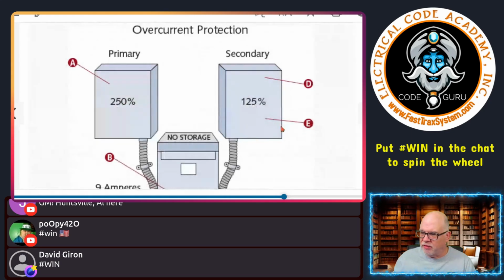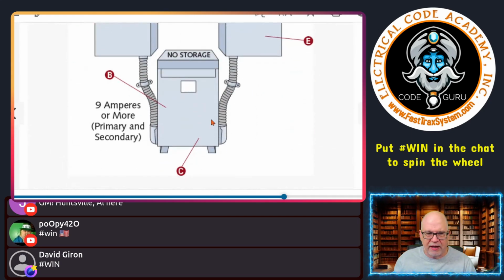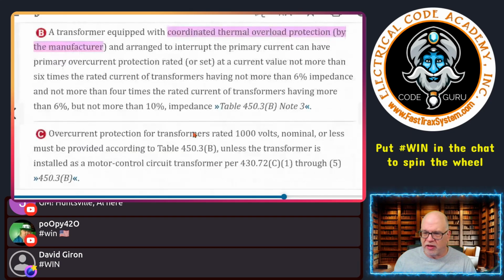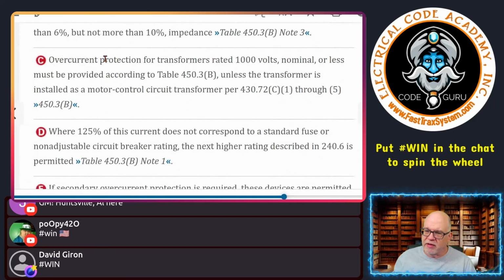C is pointing out, let's see, where's C at here? Right here, pointing out the transformer again. So C is saying overcurrent protection for transformers rated 1,000 volts nominal or less, probably the main transformers that you work with, must be provided.